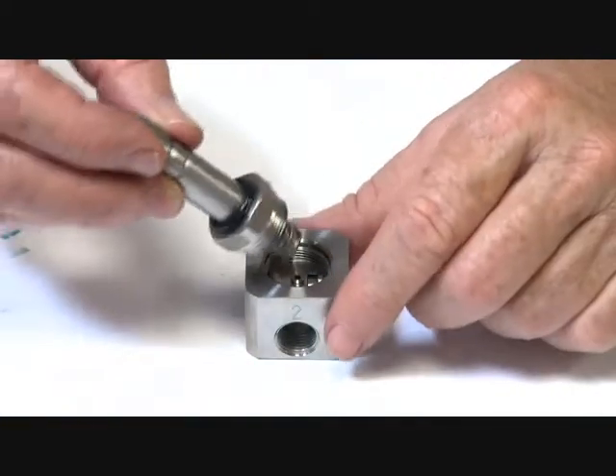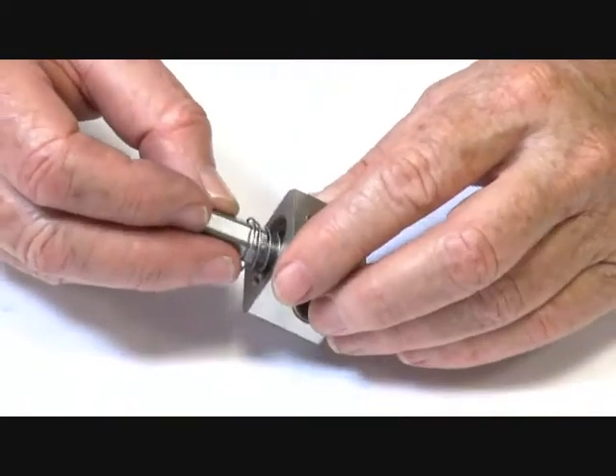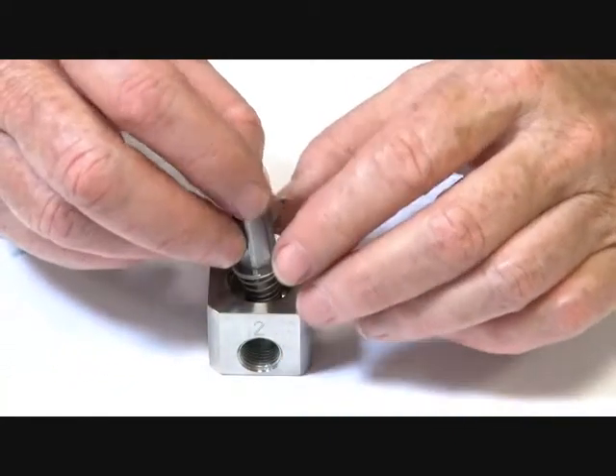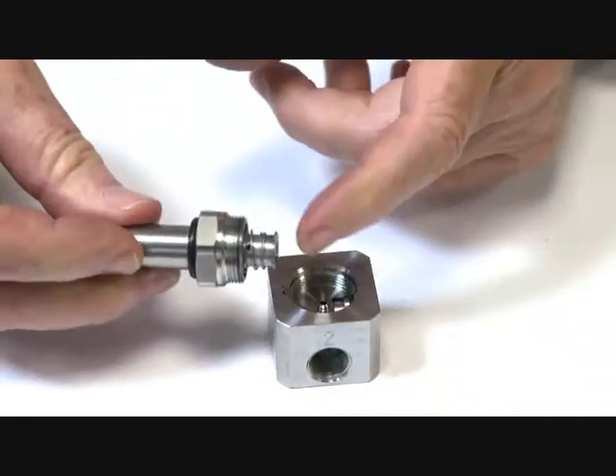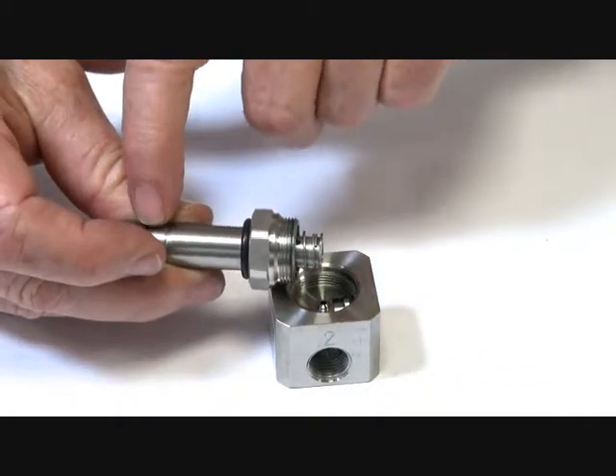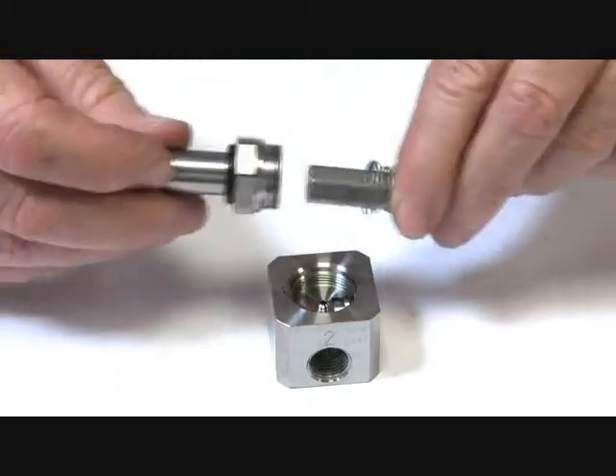The armature is normally sitting on top of that seat, blocking off the exhaust. When the valve is energized, the armature pulls up into the seat, blocking off the supply. The supply is up there with a little jet that gets blocked off by that little rubber piece.